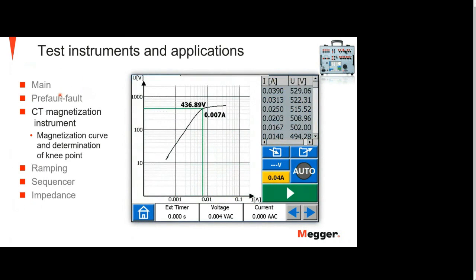This is when you're testing a current transformer and doing a CT magnetization test. So you do a magnetization curve to find out the voltage knee point of the current transformer. So you can be in automatic mode. In the automatic mode, you just push the play button. You connect, of course, according to what the screen says, how you shall connect. And then you push the play button, and then you will start injecting the voltage. It will go up the curve, automatic, and when it finds the voltage knee point, it will go down, and then it will do a more precise calculation of the voltage knee point.